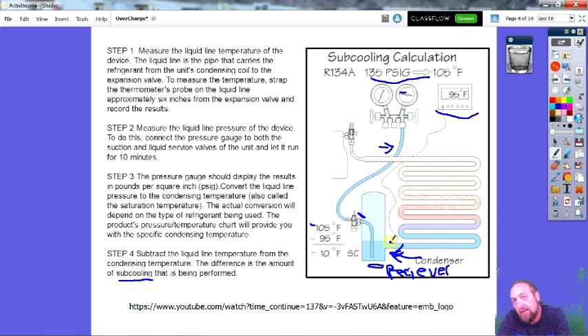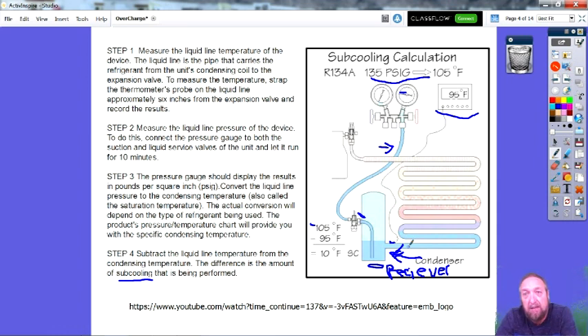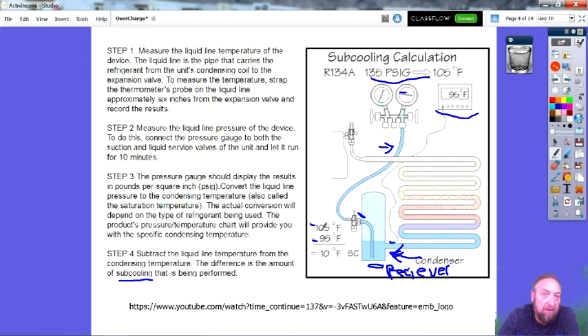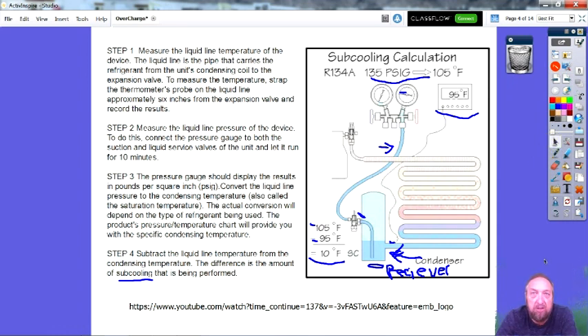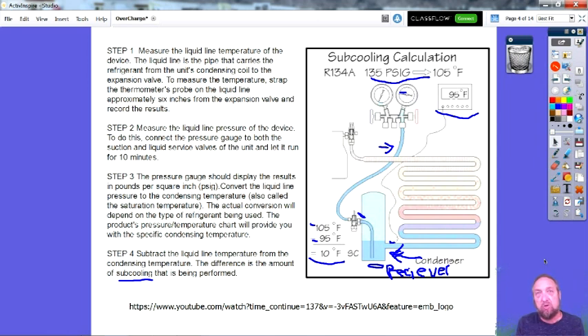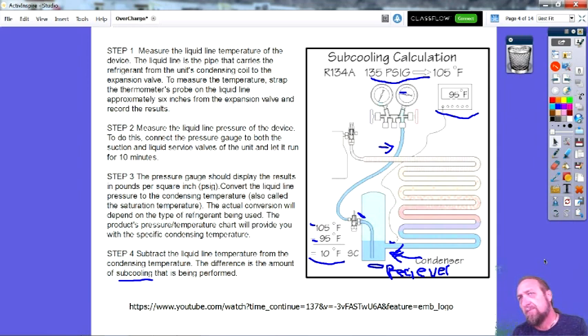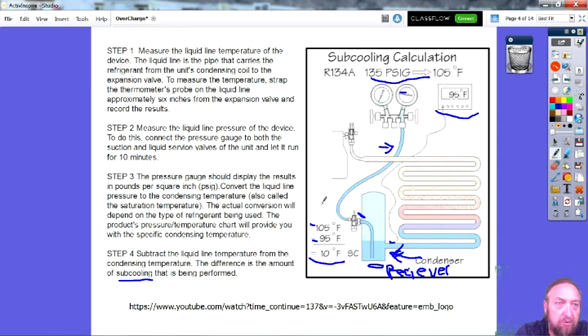The thermistor is taped to the outside of the liquid line measuring the temperature of the tube — in this case 95 degrees. Subtract this from the saturation temperature: 105 minus 95 gives 10 degrees Fahrenheit subcooling. This is another method for determining proper charge of the system. You can go by superheat on the evaporator suction line, or by subcooling on the condenser liquid line.